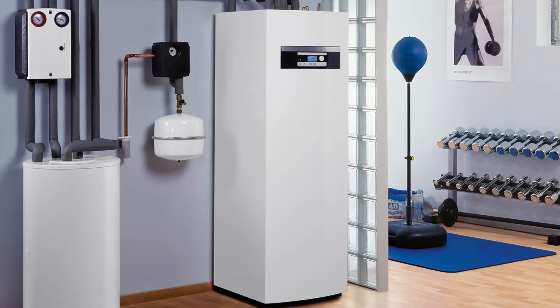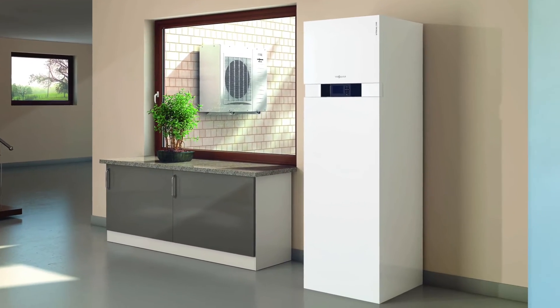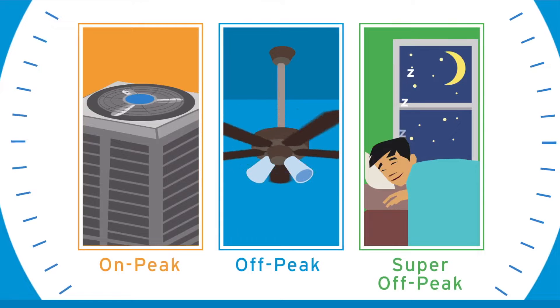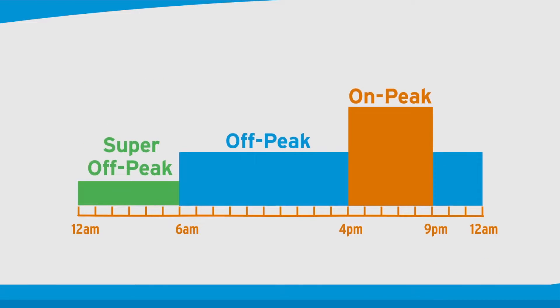If you decide on an air-to-water heat pump system, I highly recommend a water tank, as they can serve as a thermal battery. First, a heat-storage buffer tank allows you to run the heat pump when the outside temperature is highest, increasing efficiency and lowering operating expenses. Second, the heat pump can run when electricity prices are low, which can also lower operating expenses if you are on a time-of-use electricity plan, which are becoming increasingly more common.